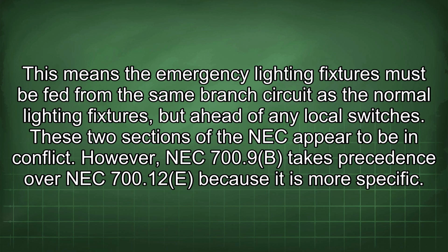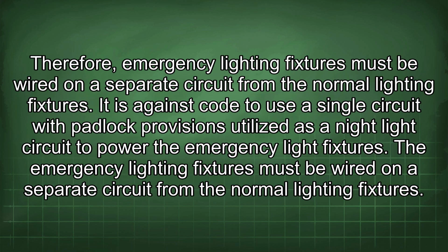These two sections of the NEC appear to be in conflict. However, NEC 700.9(B) takes precedence over NEC 700.12(E) because it is more specific. Therefore, emergency lighting fixtures must be wired on a separate circuit from the normal lighting fixtures. It is against code to use a single circuit with padlock provisions utilized as a night light circuit to power the emergency light fixtures. The emergency lighting fixtures must be wired on a separate circuit from the normal lighting fixtures.